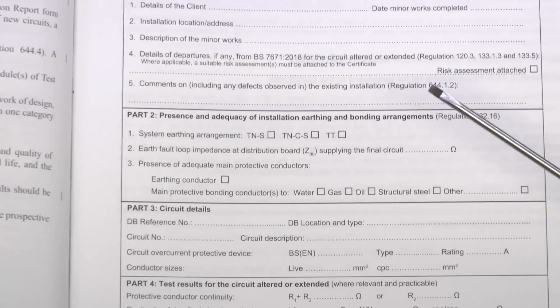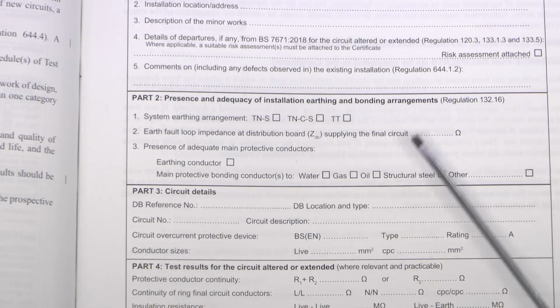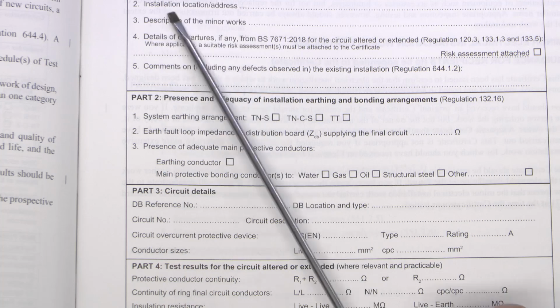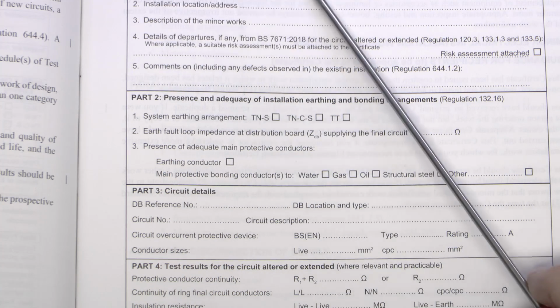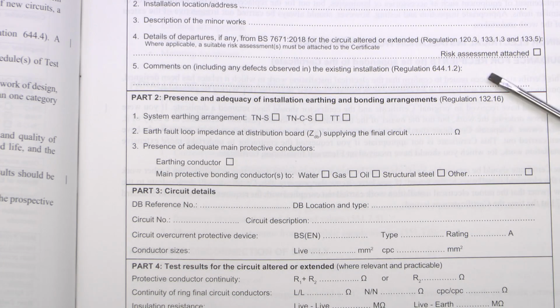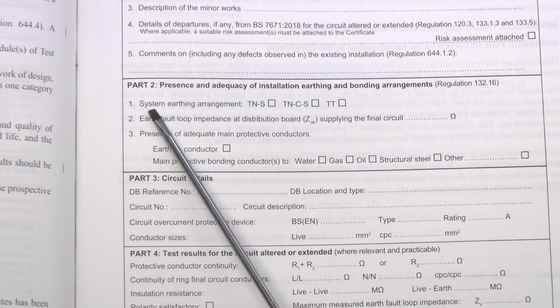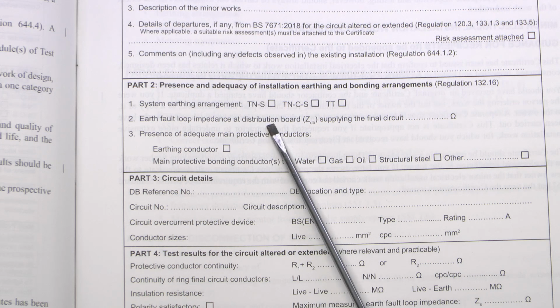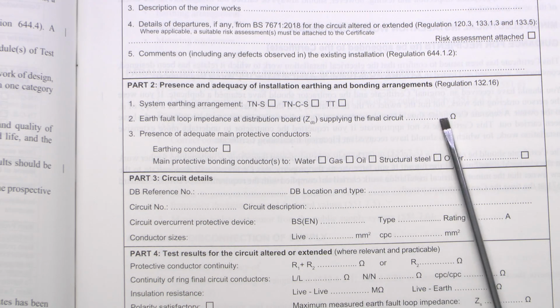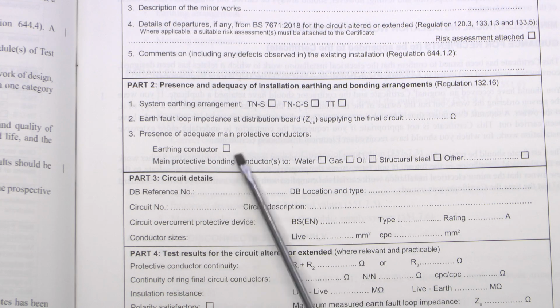The form itself has some additional pieces added. At the top, part 1 is the description and location of what you've changed. In part 2, we now have the system earthing arrangement, earth fault loop impedance at the distribution board supplying the final circuit, and again the tick boxes for protective conductors as before.